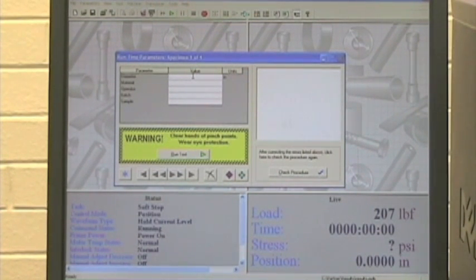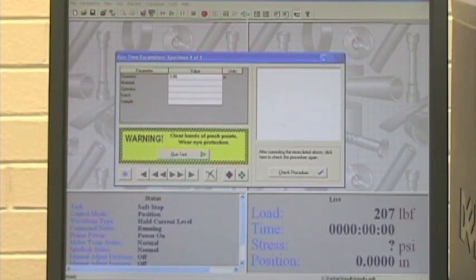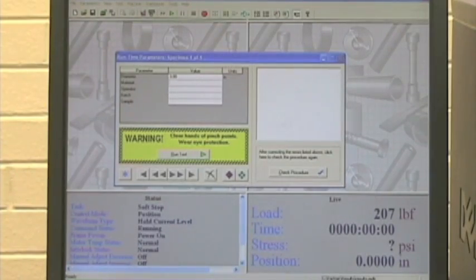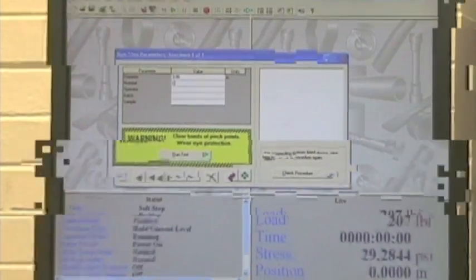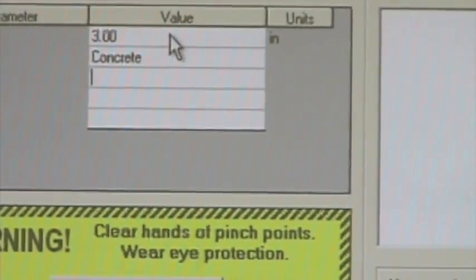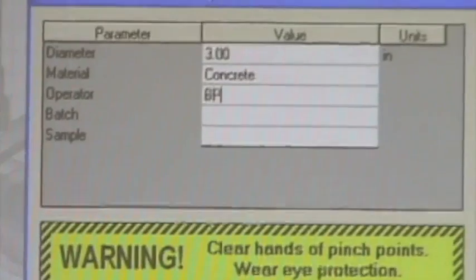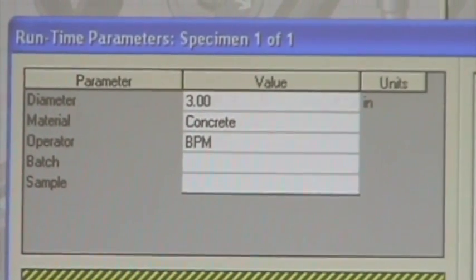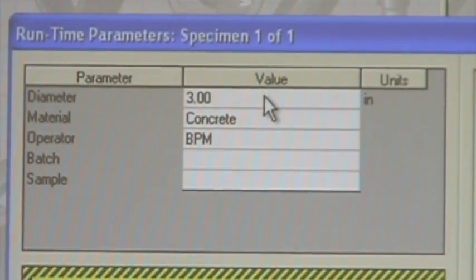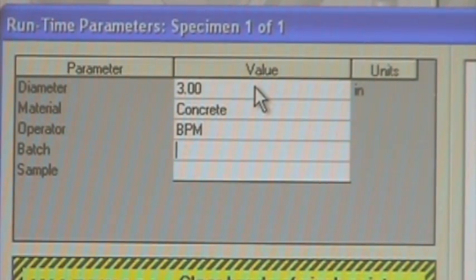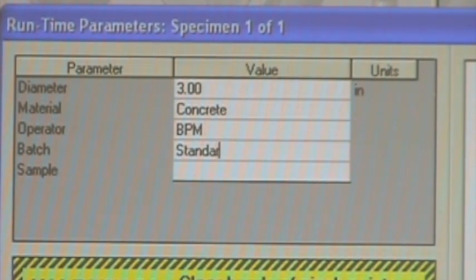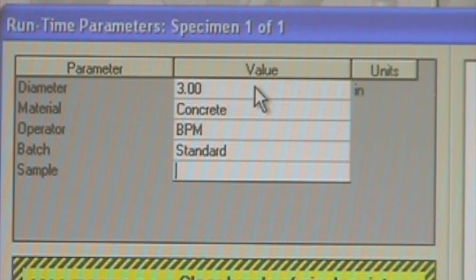So right now we're using a 3.00 inch diameter for our test specimen. The material is concrete. Operator, your initials BPM for myself. The batch, for this instance, it's going to be the standard.